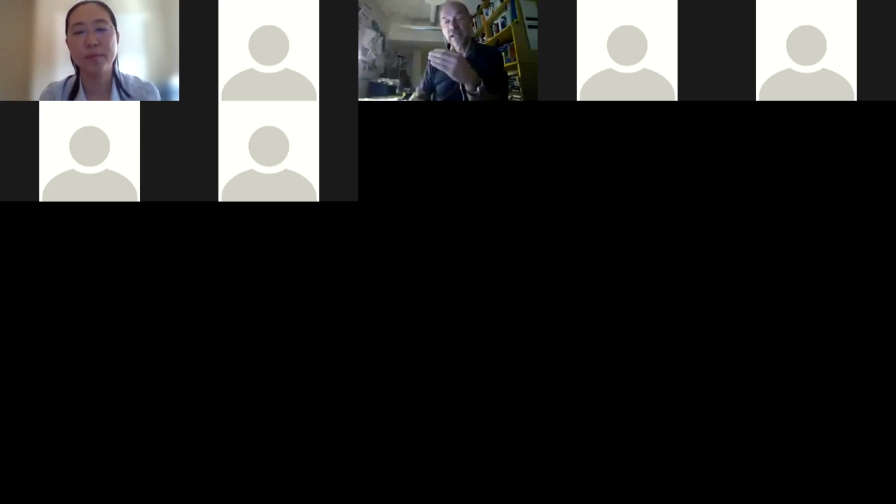So then you need to understand what could be the difference between day and night. But we can do a lot of averaging, and we can measure as much as needed. So I don't think we should call this a snapshot measurement. You can measure for a month, for 3 months, and you can average and aggregate. Definitely not a snapshot. But yeah, that's just a comment.